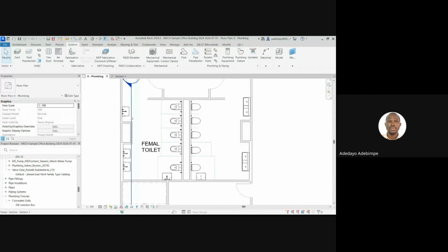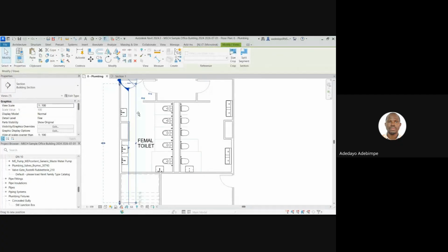In Revit, Revit can help you generate pipe routes automatically. However, it is something I strongly advise against. Reason why: Revit is not so smart in drawing those pipes. With the advent of AI, we can say, okay, maybe it's doing better, but Revit itself is terrible at giving you a desired pipe route. Now, let's experiment with that. So let's say we want to generate an automatic pipe route for all our cold water systems.